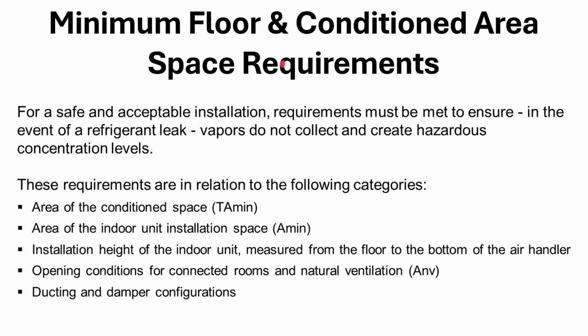Minimum floor and conditioned area, space requirements. For safe, acceptable installation, requirements must be met to ensure that in the event of a refrigerant leak, vapors do not collect and create hazardous concentration levels. These requirements are in relation to the following categories, which we talked about: area of conditioned space, area the indoor unit is installed in, so the AMIN, area minimum requirements, install height of the indoor unit, measured from the floor to the bottom of the air handler. Picture what we're talking about, there's an example coming up. SVZ upflow configuration, opening conditions and connected rooms and natural ventilation, and then ducting and damper configuration. So all requirements for this space. Again, each system will have a chart found in the outdoor service manual to determine if a system can be installed in that area.